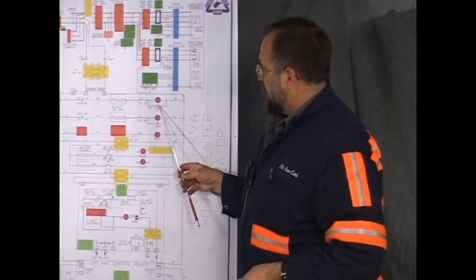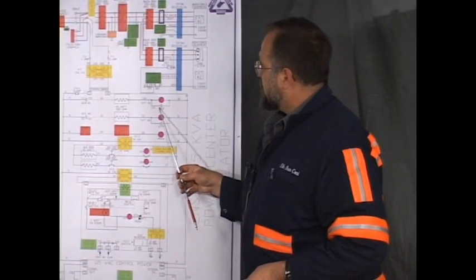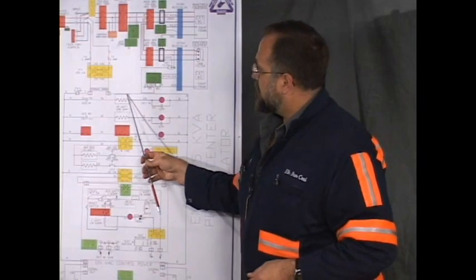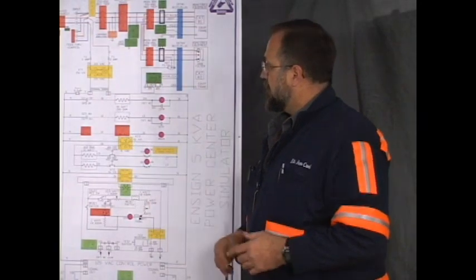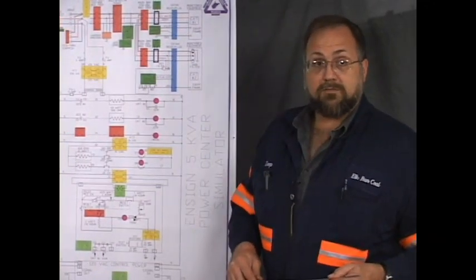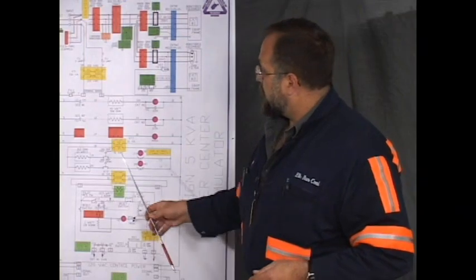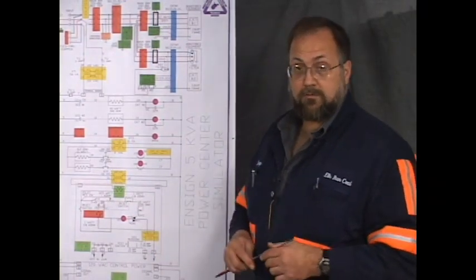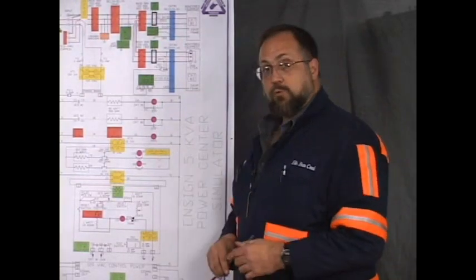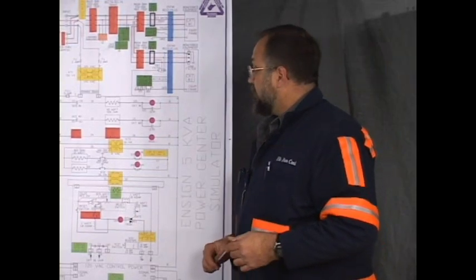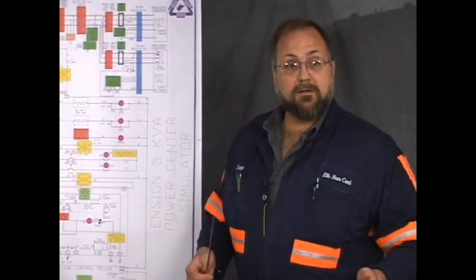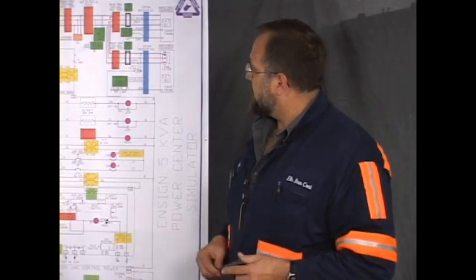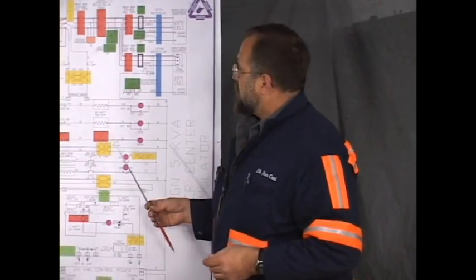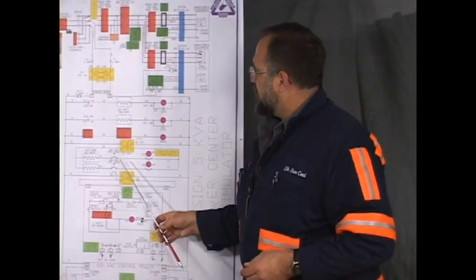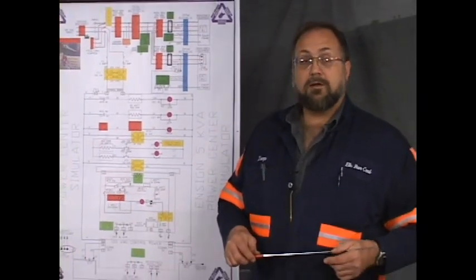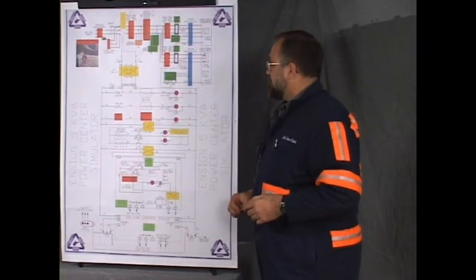When you intentionally press the test circuit, it closes these tips, and that will cause all the voltage, all the current to be dropped right here. But we don't have the test intentionally depressed. So one of two things: it can either be stuck, shorted, or these tips can be shorted, stuck. They're normally open. If they fail, and they fail in a closed status there, it's just as if you had the button depressed. So what we're going to do is troubleshoot the circuit and try to determine which one of these two problems we have. The problem illustrated that we don't have a ground fault on the power conductors for circuit number 1, so that won't be an issue.